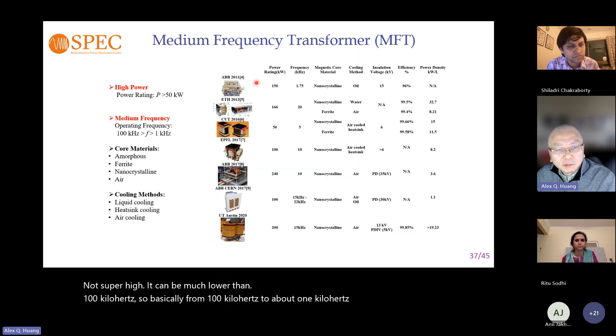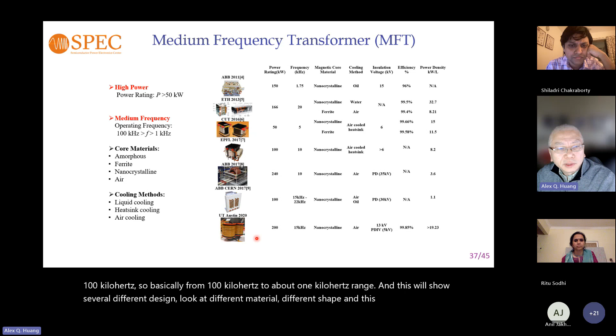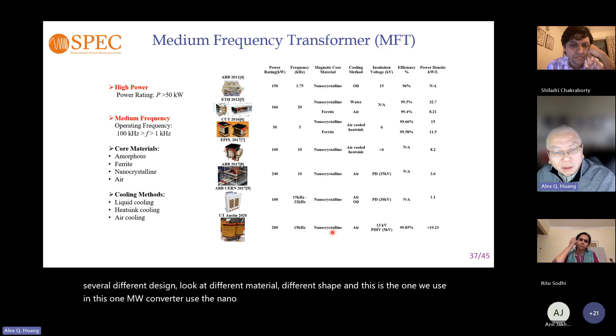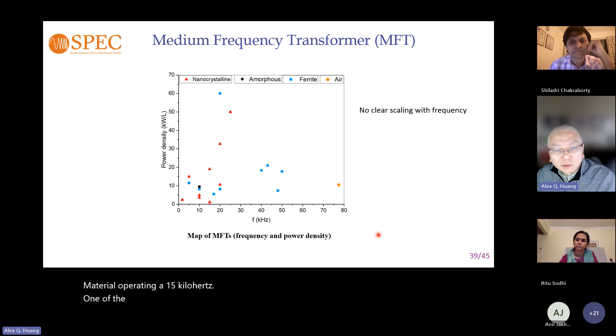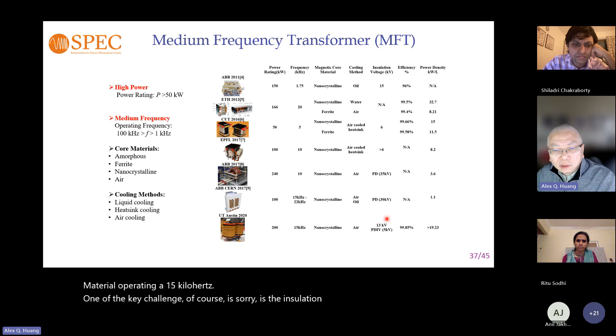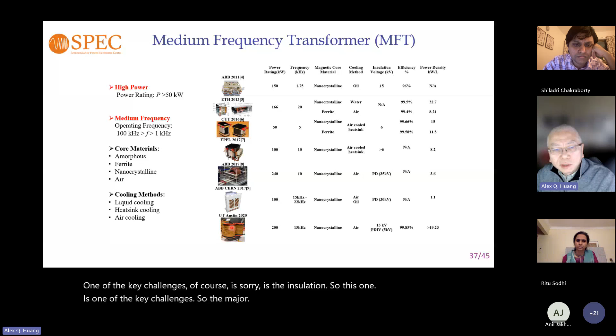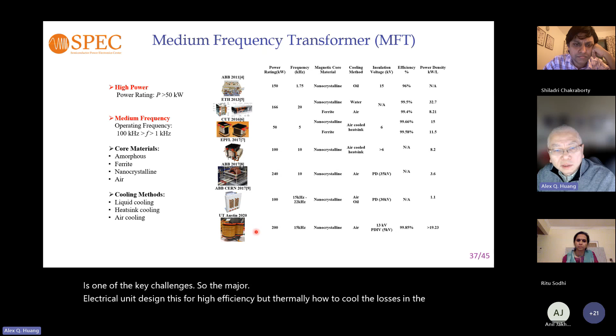This will show several different designs, looking at different materials and different shapes. And this is the one we use in this 1 megawatt converter. It uses a nanocrystal material operating at 15 kilohertz. One of the key challenges, of course, is the insulation. Electrically, you need to design this for high efficiency. Thermally, there is the question of how to cool the losses in the transformer. This is a 200 kilowatt unit, so even 1% of losses is 2 kilowatts.